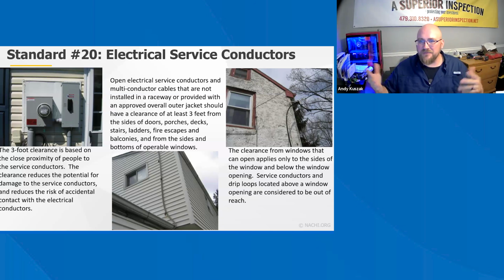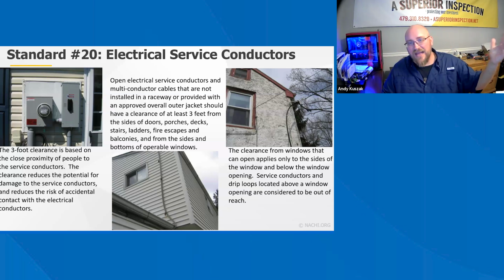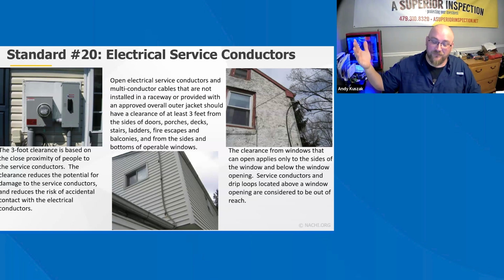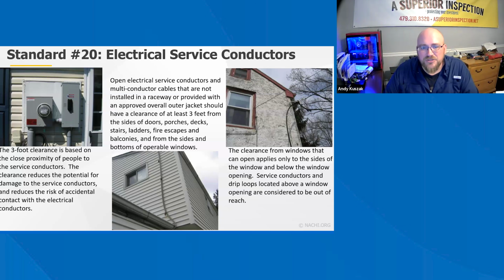A lot of times, if you have a tornado or ice damage, and tree limbs fall on your service line, that can pull the masthead down. Or in a really bad situation, maybe the electrical pole is rotting in the ground, and sometimes that pole can start to lean, and that causes the service drop to drop too. So if you don't have a method for determining the distance from the ground to the electrical service conductor, a lot of times you can only do your best guess.